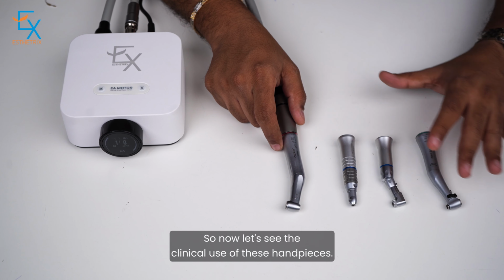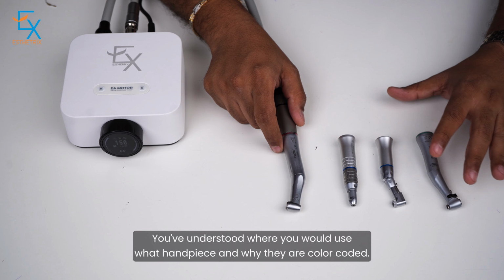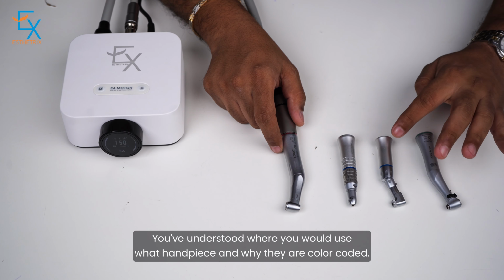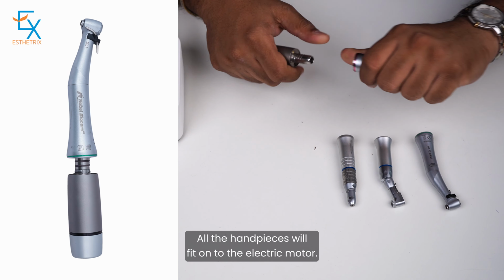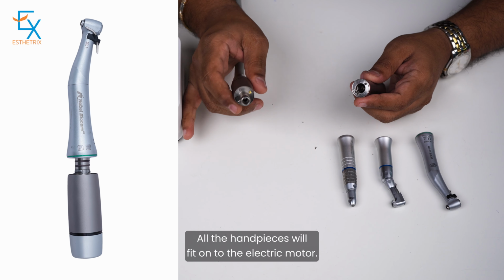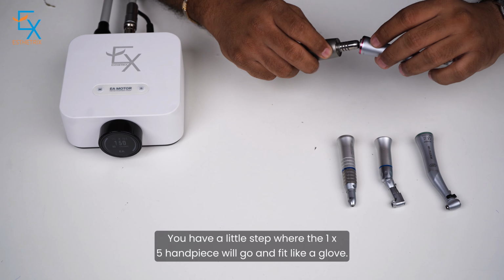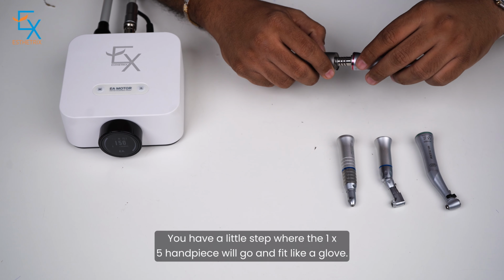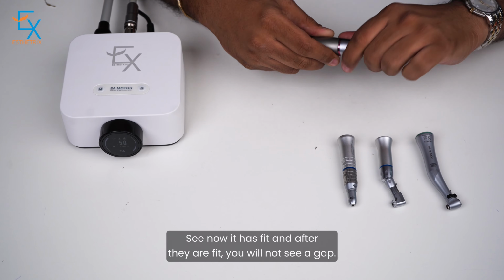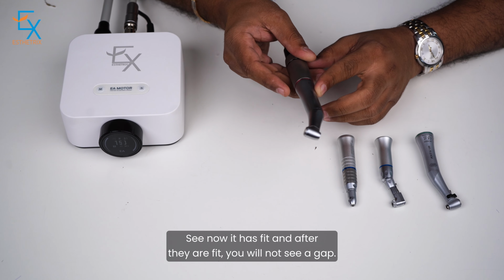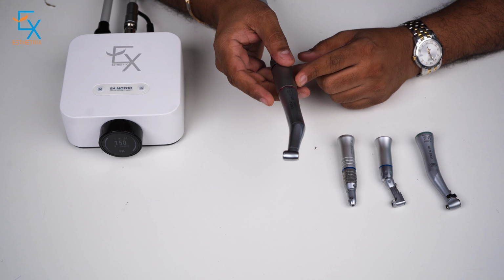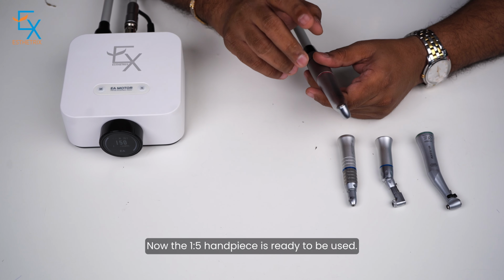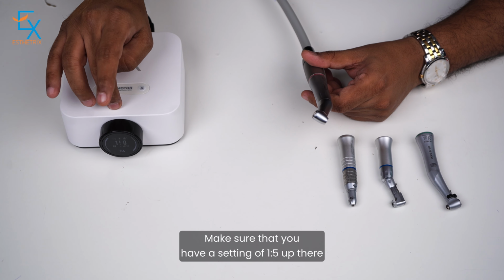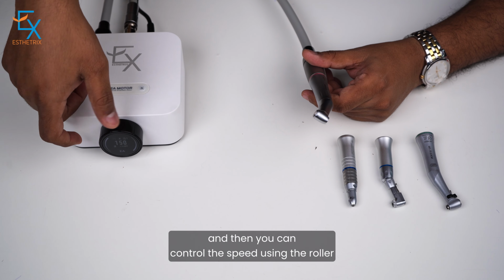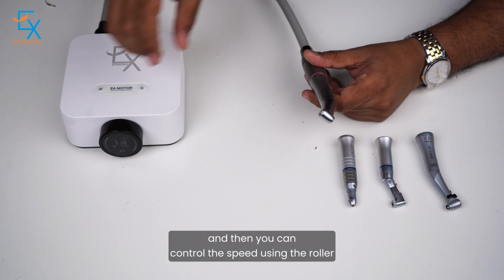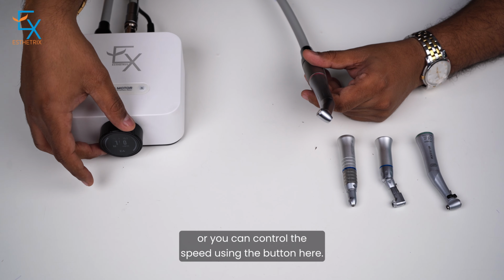So now let's see the clinical use of these handpieces. You've understood where you would use what handpiece and why they are color coded. All the handpieces will fit on to the electric motor. You have a little step where the 1:5 handpiece will go and fit like a glove. See, now it has fit, and after they are fit, you will not see a gap. It will be a seamless integration. Now the 1:5 handpiece is ready to be used. Make sure that you have a setting of 1:5 up there, and then you can control the speed using the roller, or you can control the speed using the button here.